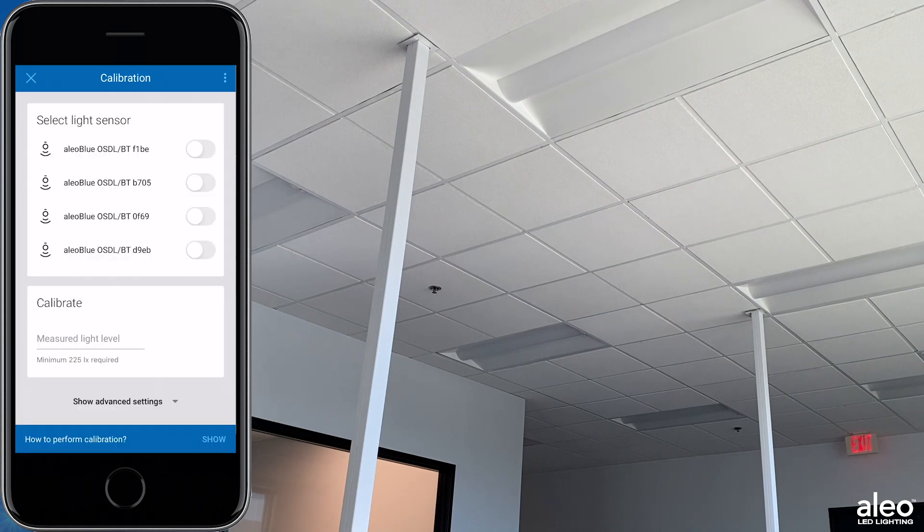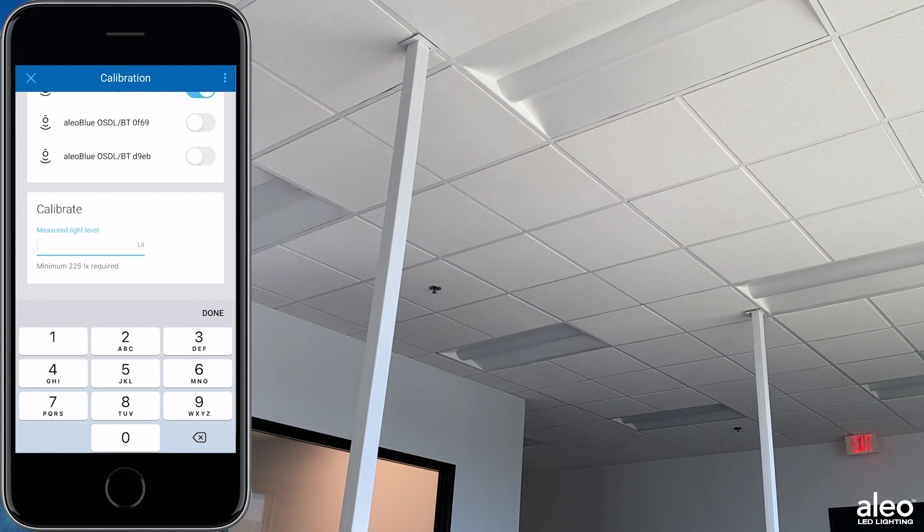Here you will enter the lux value reading from your light meter. This will allow your zone to calibrate daylight harvesting correctly.